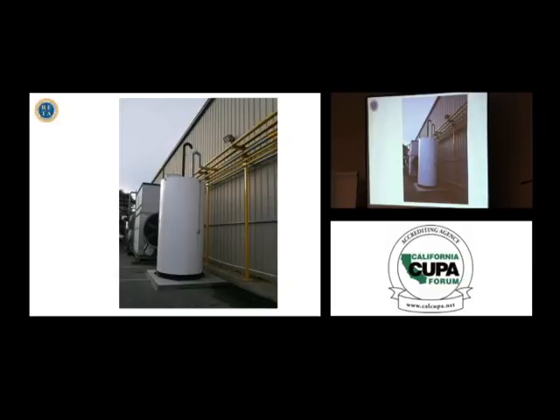There's other levels to be concerned about too. This happens to be an ammonia diffusion tank that's hooked up to the relief valves. And if the level climbs in here, there's got to be a reason. The easiest thing to find out, if we added ammonia, is to take a water sample and get the pH of it.